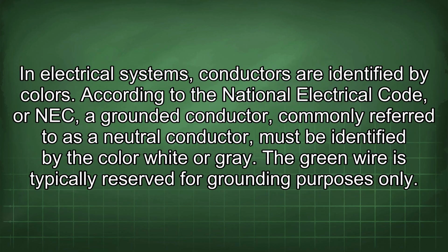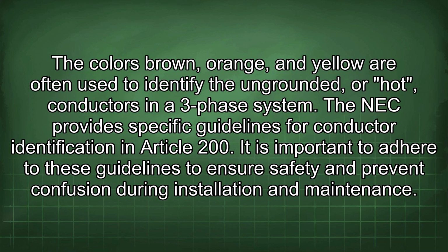In electrical systems, conductors are identified by colors. According to the National Electrical Code, or NEC, a grounded conductor, commonly referred to as a neutral conductor, must be identified by the color white or gray. The green wire is typically reserved for grounding purposes only. The colors brown, orange, and yellow are often used to identify the ungrounded, or hot, conductors in a three-phase system.